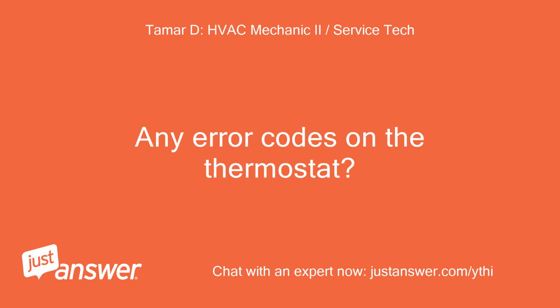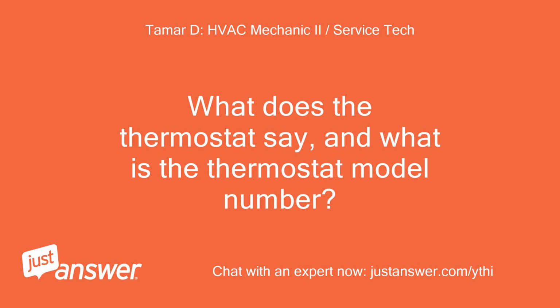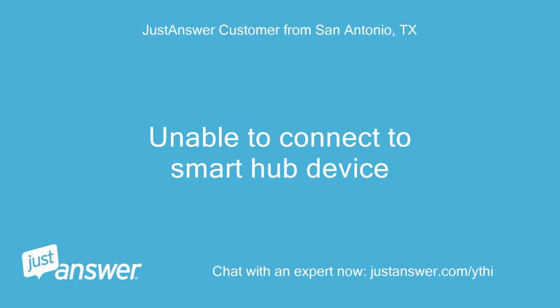Any error codes on the thermostat? The thermostat can't communicate, so it doesn't actually go to the normal display. What does the thermostat say, and what is the thermostat model number? iComfort S30HD. It says iComfort cannot communicate with the equipment. Unable to connect a smart hub device.